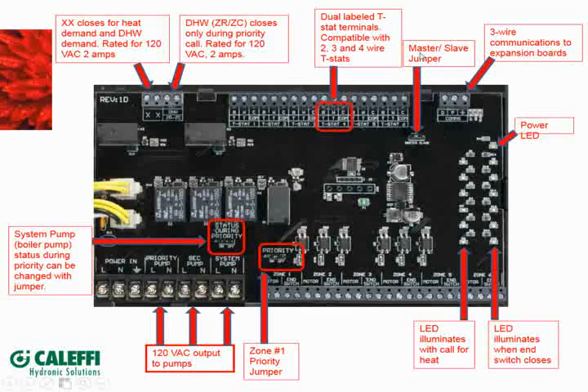We program here a little bit differently, though. We don't have the little dip switch. We're using jumpers. So you'll see here we have a master-slave jumper, and there's 3 pins. On one side, you'll see, like down here, which is a little bit better of a photo, the priority switch. You'll see an on and an off. If the center pin is jumpered over to the on, obviously priority is on. You pull that jumper out and put it between the center pin and off, then it's off. Or if you simply pull the jumper off, it means it's off. You don't necessarily have to have a jumper in for it to work.